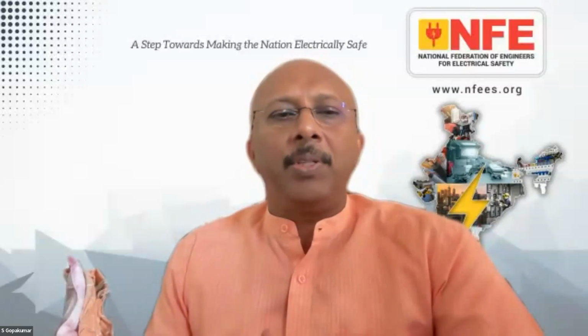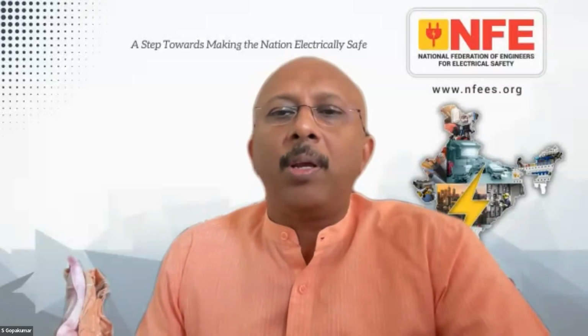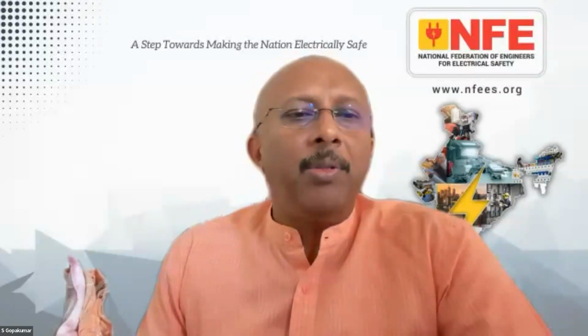Yes, yes. Power cable and earth strip normally is taken within the shaft, except for fire rated elevators, where they specify that it should be taken from outside. Okay, okay. Because the purpose demands it, it has to work, and the fire should not penetrate to this particular area. Yes, yes, yes. That is the idea.